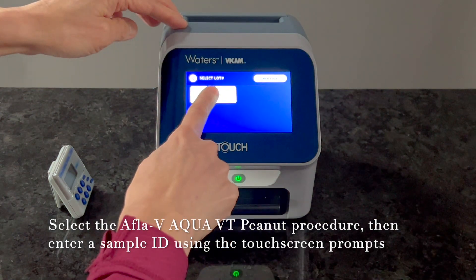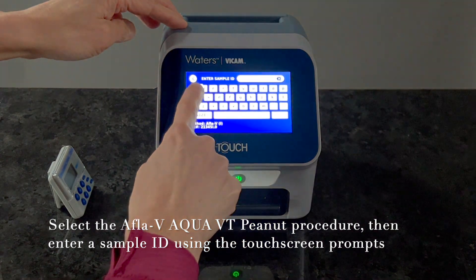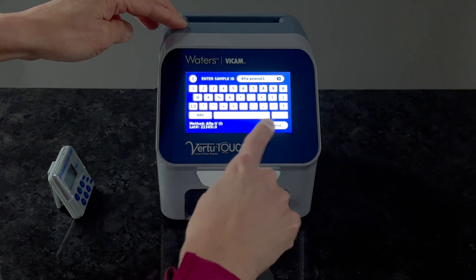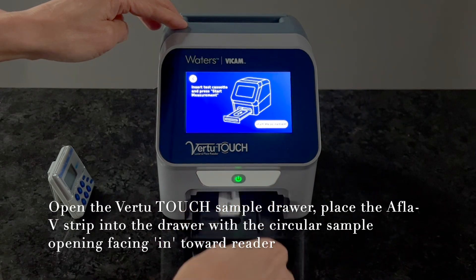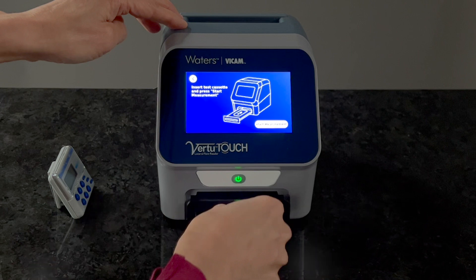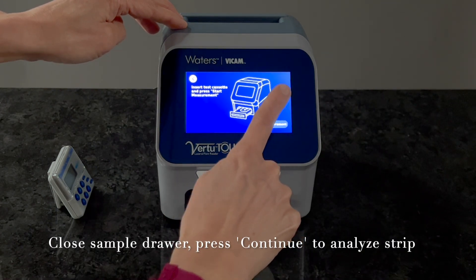While the strip is developing, select the Afla-V AQUA VT Peanut method from the Vertu-TOUCH Reader menu, entering a sample ID when prompted. Open the Vertu-TOUCH Reader sample drawer, placing the Afla-V strip into the drawer with the circular sample opening facing toward the reader. Then close the drawer and press continue to analyze the test strip.